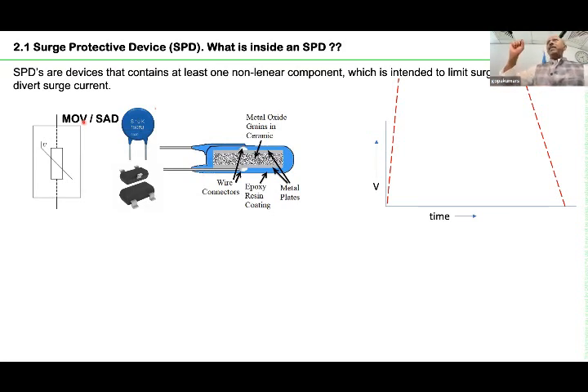So that means if this device is connected between line and neutral, parallel to the line, during normal condition, 230 volt or 240, 250, up to 300 volt, nothing happens. The device is offering a very high insulation or very high resistance. But once the voltage crosses, for example, 1.5 kV or 2.5 kV, then suddenly the resistance offered by the device is very small. As a result, line and neutral are almost connected. I have a picture, I will show it later. So MOV based devices are called voltage clamping type devices.